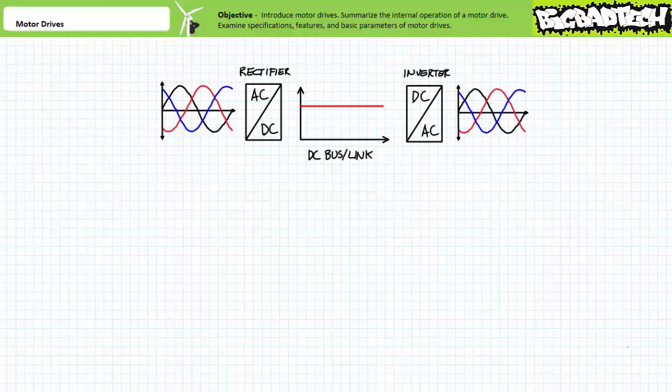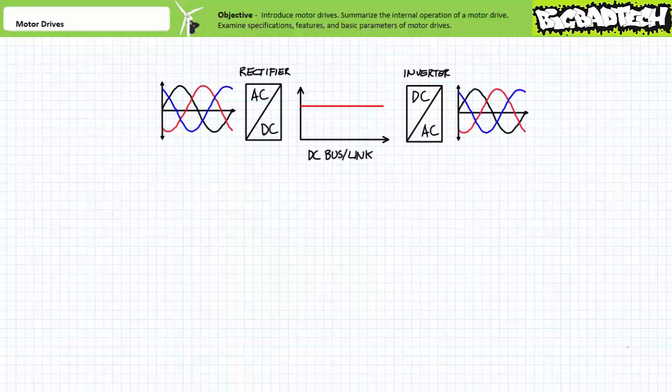When viewed at this level of detail, a motor drive is a rectifier — an AC-to-DC converter — followed by an inverter — a DC-to-AC converter. For this reason, motor drives are somewhat mistakenly referred to as inverters, which actually only describes one half of their purpose. The DC voltage between the two related power electronics stages is known as the DC bus or DC link, which can store tremendously large values of DC voltage. For example, a motor drive operated on 120V line-to-neutral and 208V line-to-line three-phase AC might have an average DC bus value of over 280 volts.